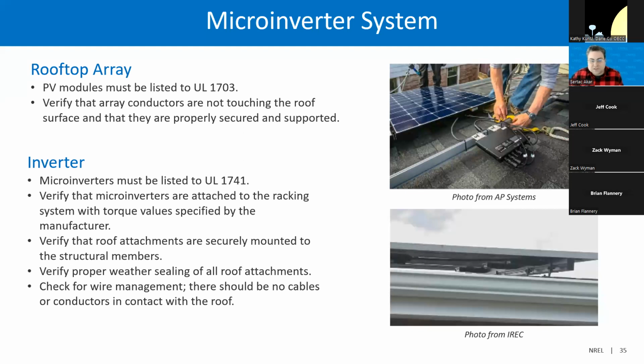When the inspector starts the inspection, the first things to inspect are the rooftop array and the inverter. PV modules must be listed to UL 1703 and the microinverters must be listed to UL 1741. Array conductors must not touch the roof surface, and they must be properly secured and supported. Conductors that touch the roof are subject to damage and cause system failures and arcing fires. Conductors must be protected from prolonged exposure and must have the proper bend radius and not be strained. The microinverters must be attached to the racking system with torque values specified by the manufacturer. The roof attachments must be securely mounted to the structural members with proper weather sealings.